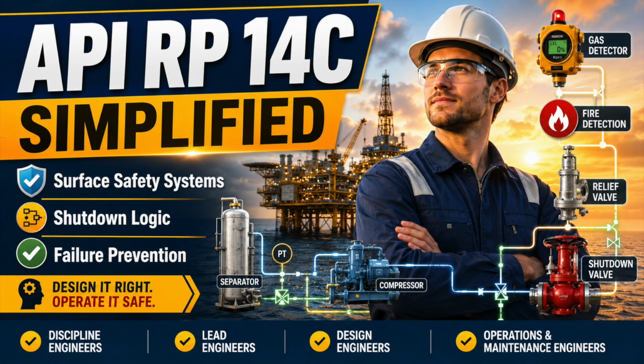Once the undesirable event is clear, identify its causes and detectable symptoms. A blocked outlet creates high pressure. A vessel leak may create low pressure or low level. A failed level control loop may create high level and liquid carryover. Excess liquid withdrawal may create low level and gas blow-by. A heater with insufficient flow may develop high process temperature. A compressor valve failure may produce high discharge temperature.